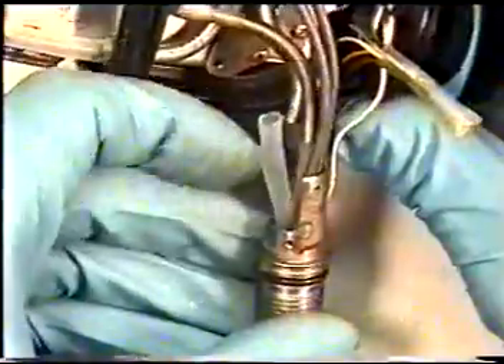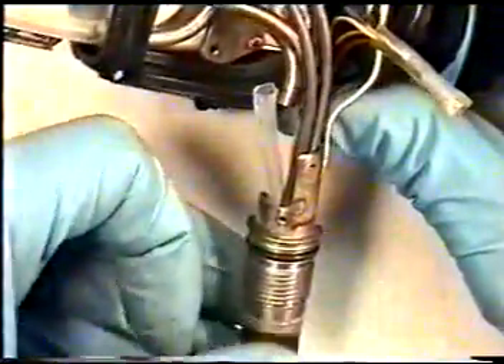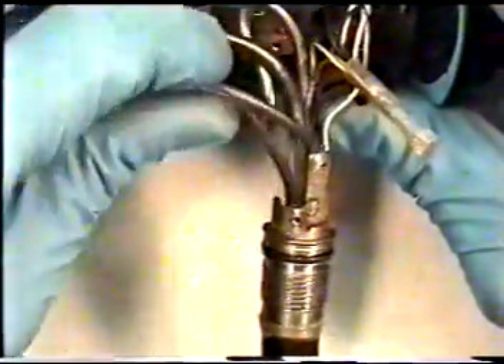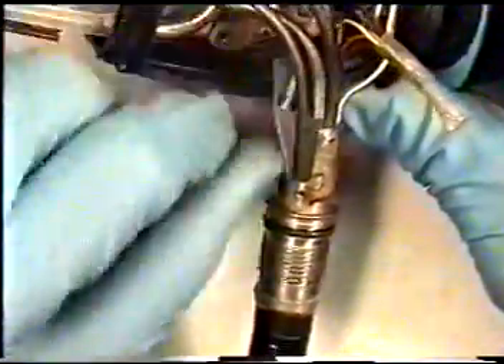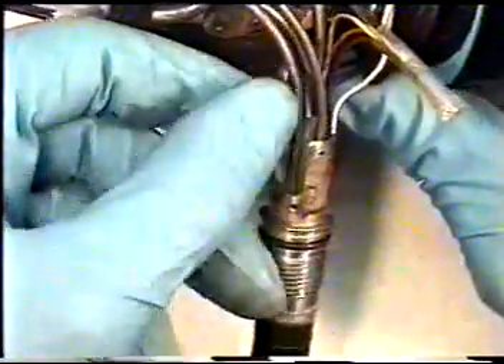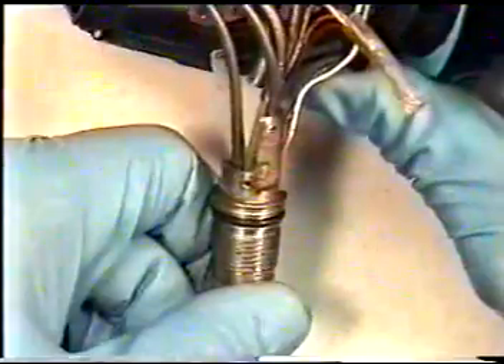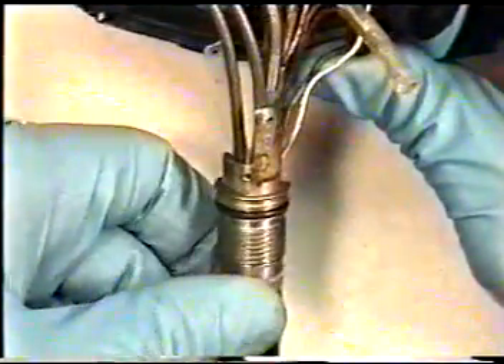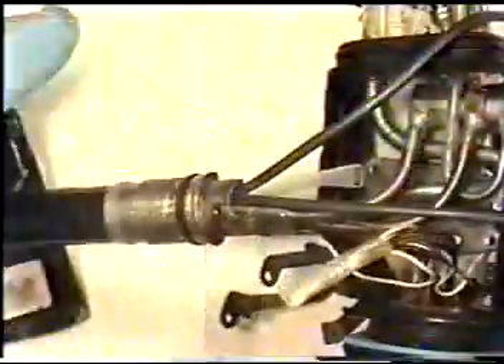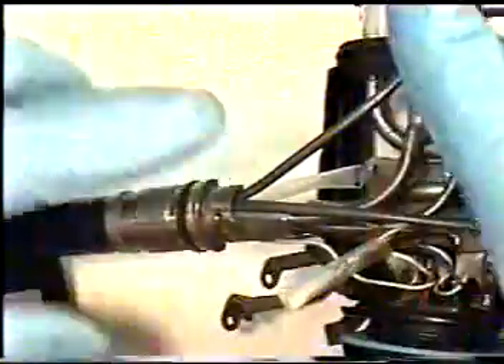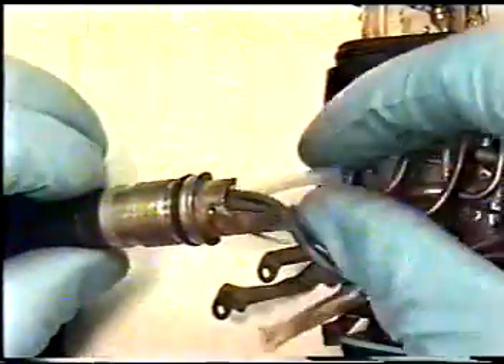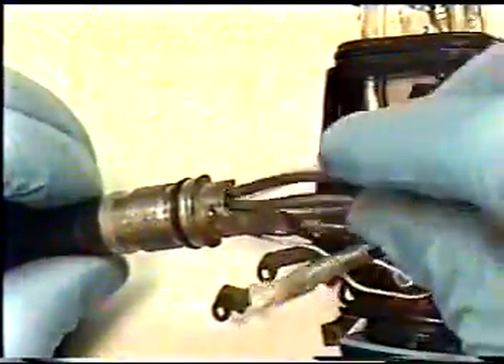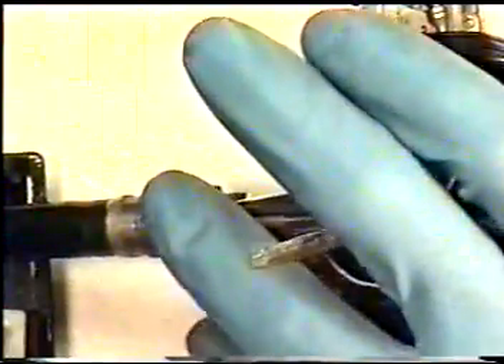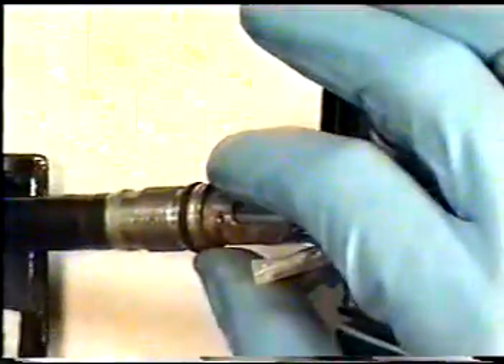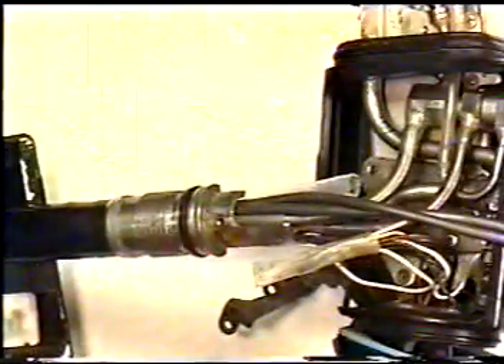We will now pull our suction channel from inside our umbilical control section in order to pull through our old damaged light guide bundles and pull in our new light guide bundles without causing damage to them, because it is too tight of a fit inside the internal structure of the light guide tube. Turn the scope around at a 90-degree angle so we can safely remove our suction channel and our old light guide and pull in our new light guides. Lay the light guide umbilical tube flat and straight along your working area all the way down to your connector.